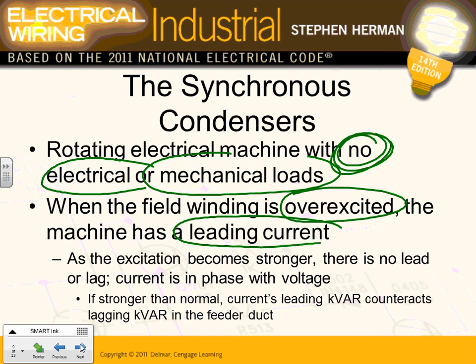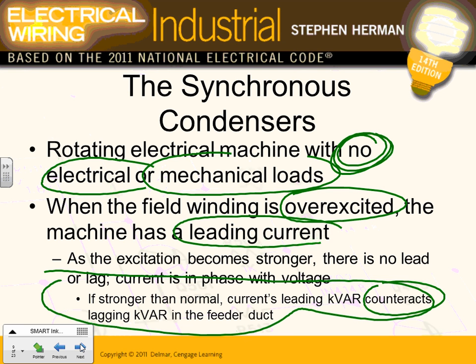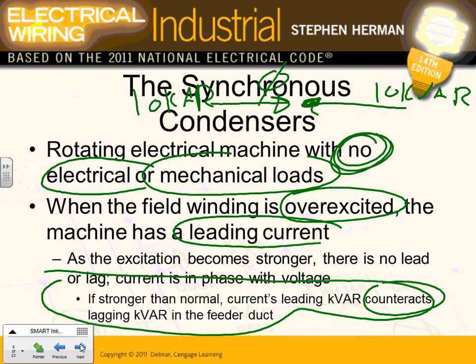The stronger the normal current leading kVAR, the more it counteracts the lagging. This is how it works. It counteracts the lagging kVAR. For example, I have a 10 kVAR leading and another 10 kVAR lagging. You put them against each other, the outcome is big fat 0 kVAR, not leading, not lagging, right? They push against each other, they neutralize each other. Any comments, guys? Any questions? Examples coming tomorrow. A detailed example about the calculation is coming tomorrow.